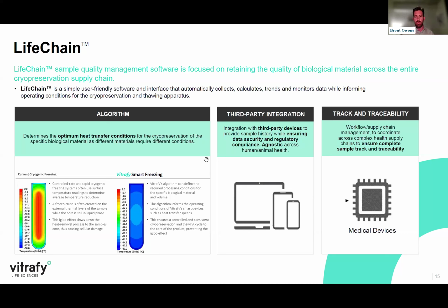One of it is the algorithm, which you can see pictured here on the left. It's a little bit of our secret sauce. And what it does is, in the founding days, we identified problems within the sample when it was cryopreserved. Through the development of the algorithm, which takes in a series of inputs, such as the sample type, the volume of the sample, how the sample behaves, and how it needs to be cryopreserved, the algorithm will then run a process to determine what cryopreservation conditions are best for that sample.